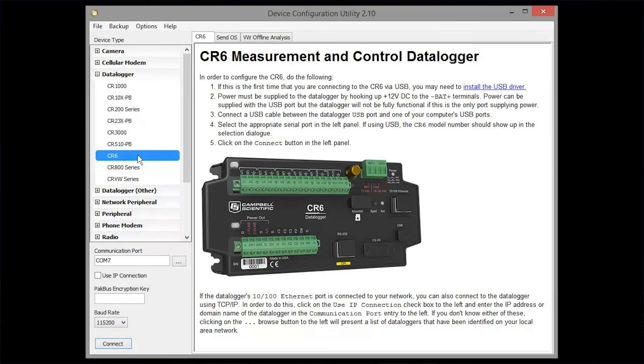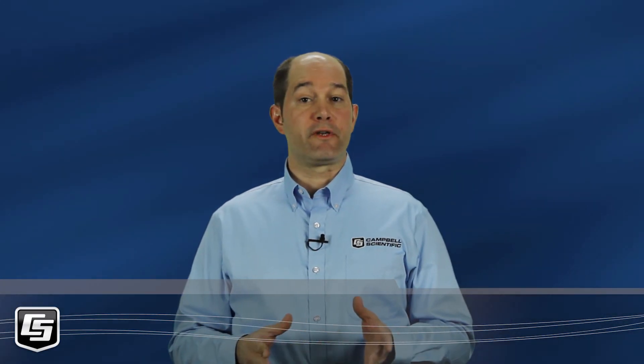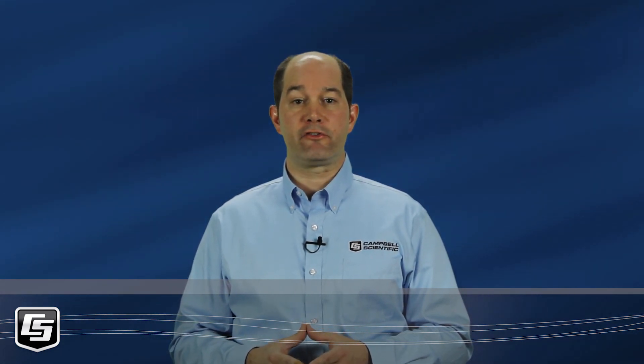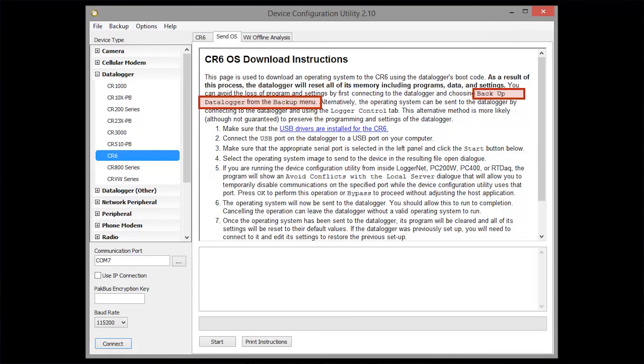Other CR Basic data loggers will also need 12-volt power. Go directly to the Send OS tab. This method of setting an OS will delete all settings and programs. If you want to easily restore these, use the backup data logger feature. This is an optional step, but I'll walk you through it.